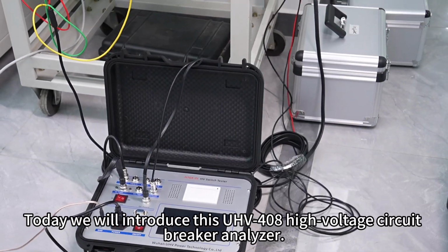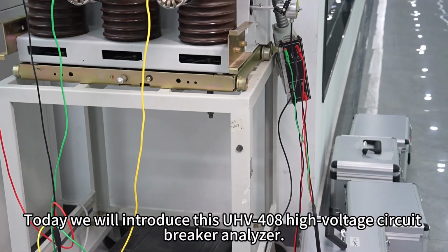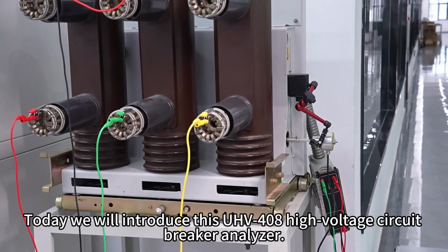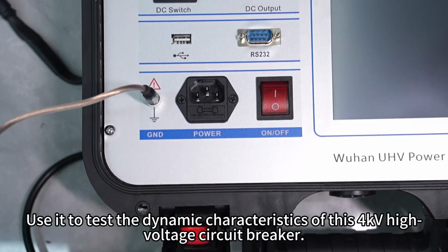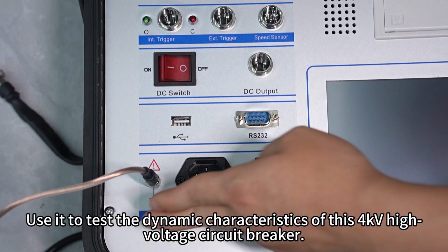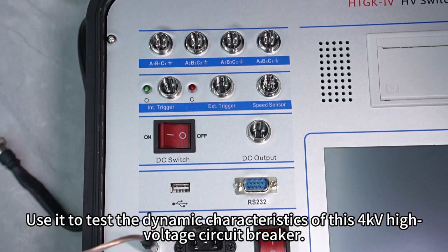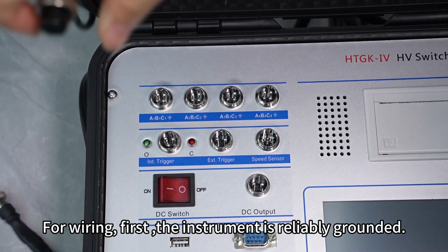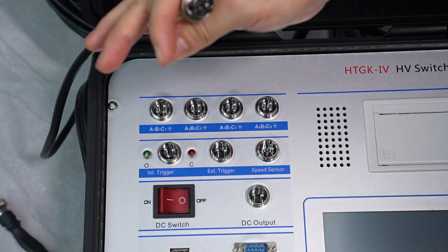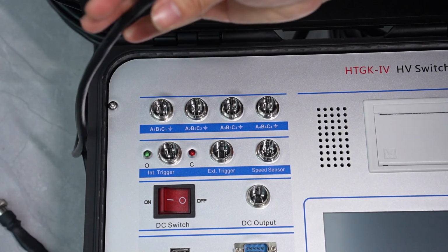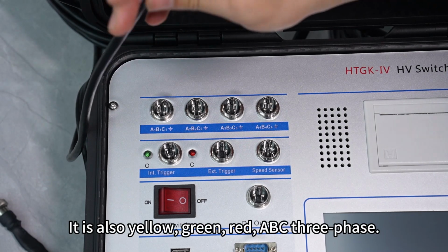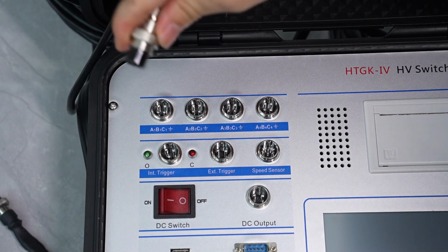Today we will introduce this UHV-408 high-voltage circuit breaker analyzer. Use it to test the dynamic characteristics of this 4 kV high-voltage circuit breaker. For wiring, first, the instrument is reliably grounded. This is a 4-core wire. It is also yellow, green, red, ABC 3-phase, with a common end.